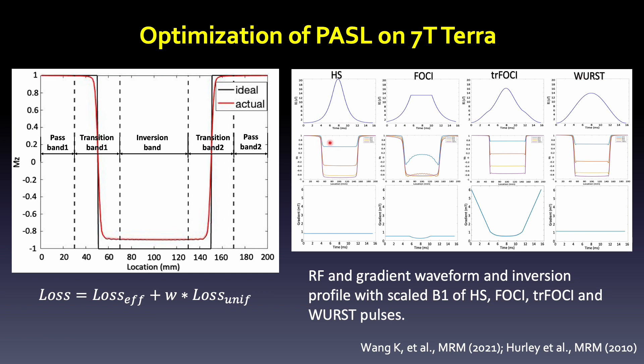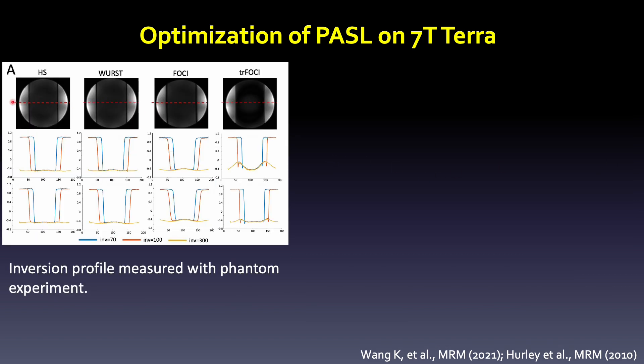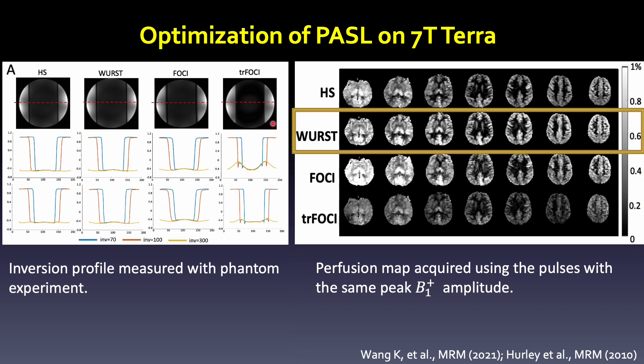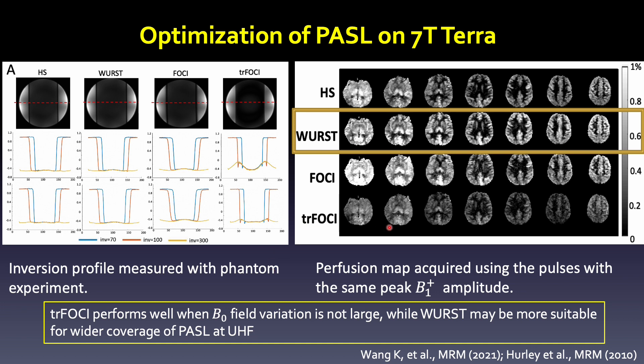Here are their waveforms as well as their simulated profiles at different B1 magnitudes. Here is the inversion profile in a gel phantom with equal SAR and equal B1 magnitude. Here are the in vivo results using these four different adiabatic pulses. Our results have shown that the WURST pulse performs most optimally in terms of inversion efficiency as well as inversion band uniformity. Literature on the trFOCI pulse shows it performs optimally when B0 field variation is not large. Our suggestion is that WURST may be more suitable for wide coverage PASL.